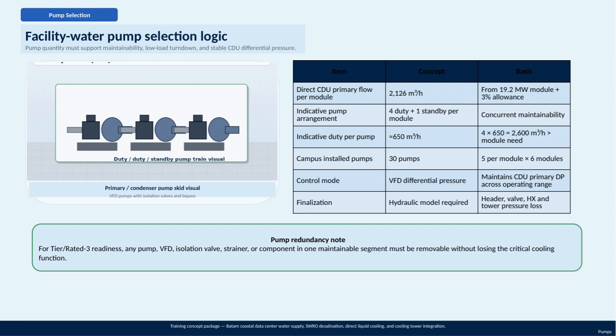A critical note on redundancy: to meet Tier or rated 3 readiness, any component, whether it's a pump, VFD, isolation valve, or strainer within a maintainable segment, must be removable without losing the critical cooling function. This ensures continuous operation even during maintenance or unexpected failures.